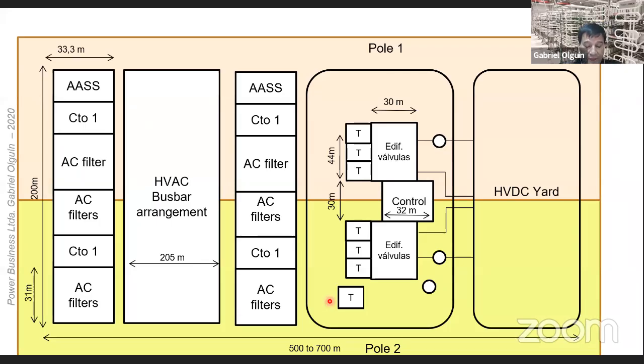Station layout. Converter station equipment can be arranged in various ways. Usually the station is clearly divided per pole, as you see here, one pole and the second pole. The dimensions are mainly determined by the rated power, voltage, and redundancy. The largest part of the station is HVAC, with reactive power compensators and filters. The second largest part is the valve hall and the converter transformers. And finally, the HVDC yard.